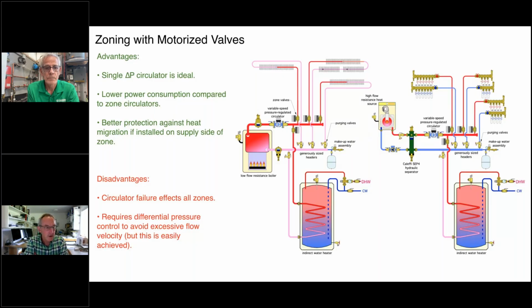One of the things you see here in the lower left, it says requires differential pressure control to avoid excessive flow velocity. If we have a fixed speed circulator, every time we close a zone down, the differential pressure increases across the zones that are still open. And with 3 or 4 zones, you don't tend to feel too much of that. But when you have a lot of zones going and only, let's say you had a 10-zone system and only 1 zone is open and it's a fixed speed circulator, now you're going to get into potential velocity problems.